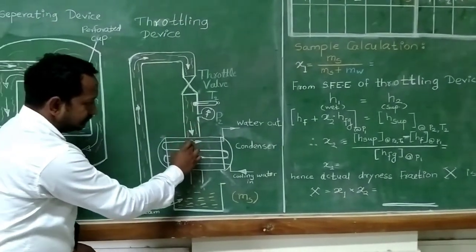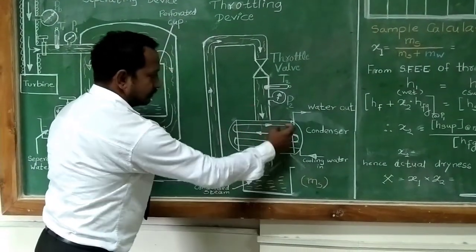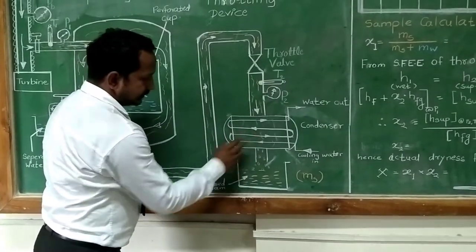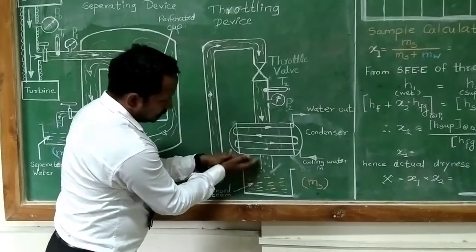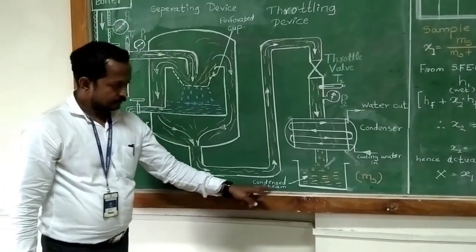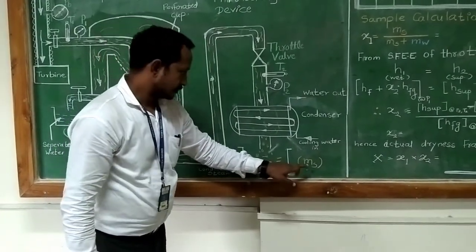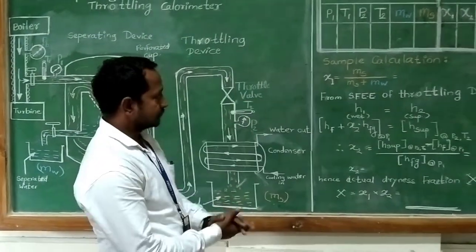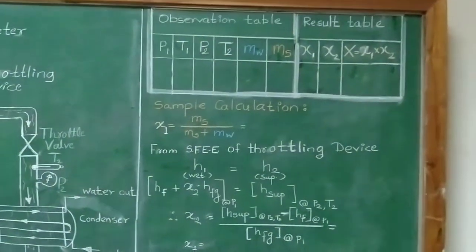Further, the steam is given to a condenser, where some cooling water is already flowing through the pipeline of the condenser. The steam which is coming out of the throttle valve is then given to the condenser. There is heat exchange, and that steam is converted into liquid form — we can say the steam is condensed. The mass which is measured here is denoted as Ms. Now, let us go to the calculations — what are the formulas and how we are going to calculate the dryness fraction of the steam using this device.